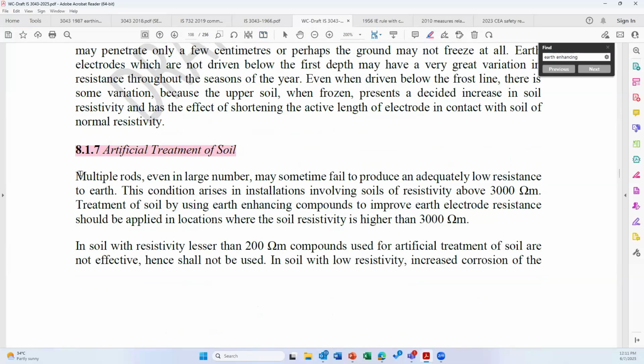Artificial treatment of soil. Multiple rods, even in large number, may sometimes fail to produce an adequate low resistance to earth. Please note that you don't need a low resistance earth electrode. That is point number one. Except 10 ohm for a type A earth electrode in case of lightning protection. This condition arises in installation involving soil of resistivity above 3000 ohm meter. That means if the soil resistivity is below 3000 ohm meter, you don't need this particular thing. Treatment of soil by using earth enhancing compound to improve earth electrode resistance should be applied in locations where the soil resistivity is higher than 3000 ohm meter.